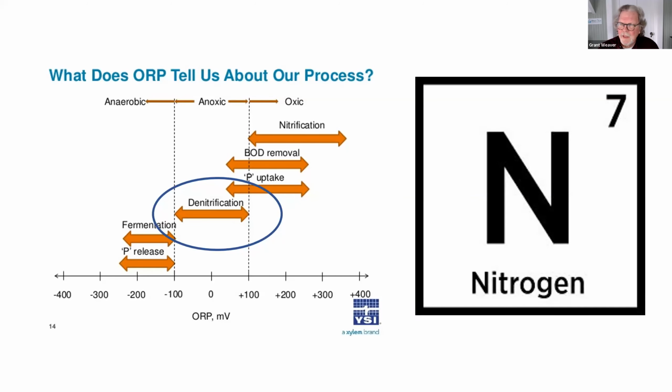This is kind of interesting here. We're going to be consuming BOD now in a non-aerated zone. They're going to be breathing that dissolved oxygen off of the nitrate, which means we're going to get some free treatment. We put in surplus oxygen to get the ammonia removal. If we can have a pre-anoxic zone, cycle through an air-off zone, we can actually ratchet down our overall oxygen requirement because we're going to lower the amount of BOD that's going into that aerobic zone.